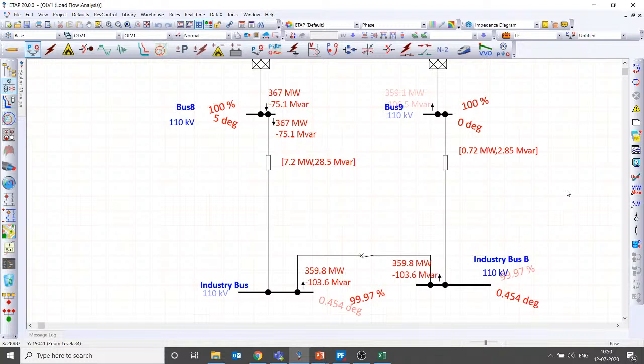You should not connect multiple grids at your industry if you have something like this. But when you have a state and you're modeling the state, and say the state has interconnection with many other states at multiple points, then the question is whether to model that as a grid, that is a multiple swing bus, or not. Answer: you can look at the real-time scenario, what the power flow is between these transmission lines, and you can put up a load with that power flow as a connection point rather than having multiple grids. Or else if you have decided to go with multiple grids, then you have to select the right phase angle and voltage magnitude so that the power flow matches the real-time scenario. Hope that is clear, Sasikumar.